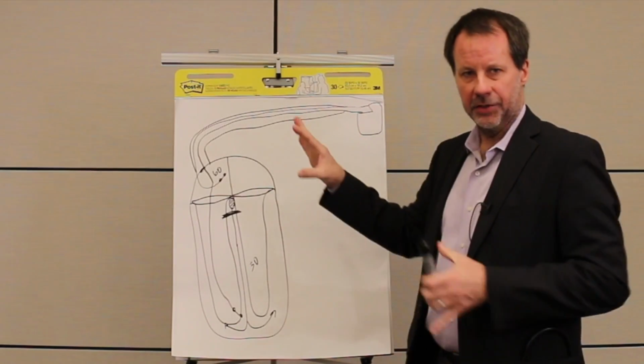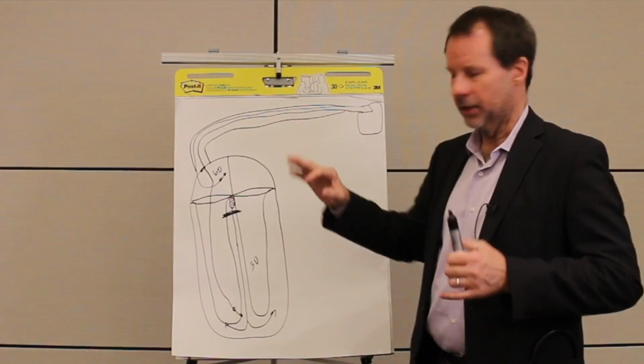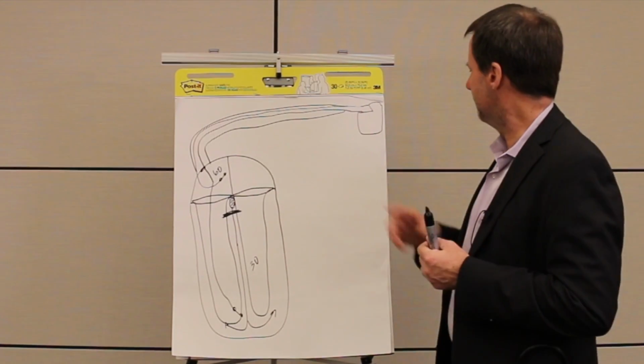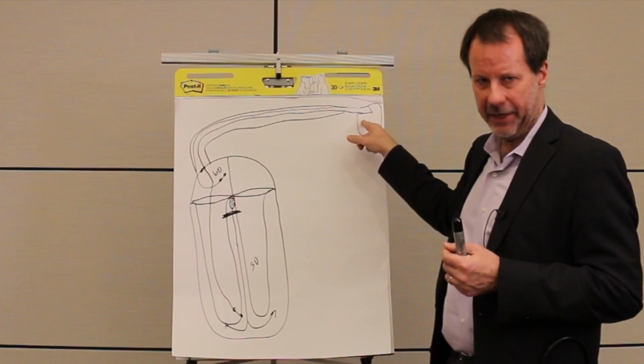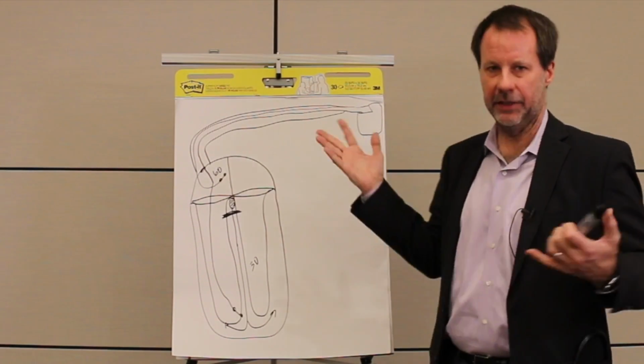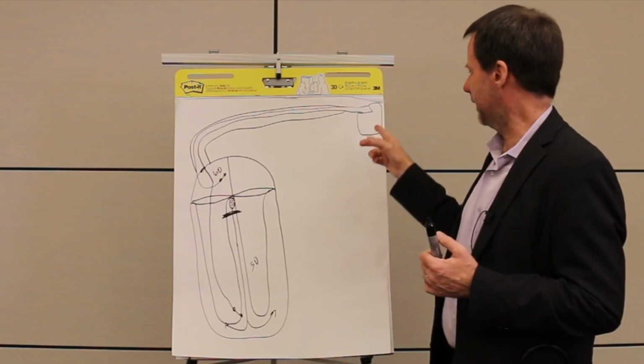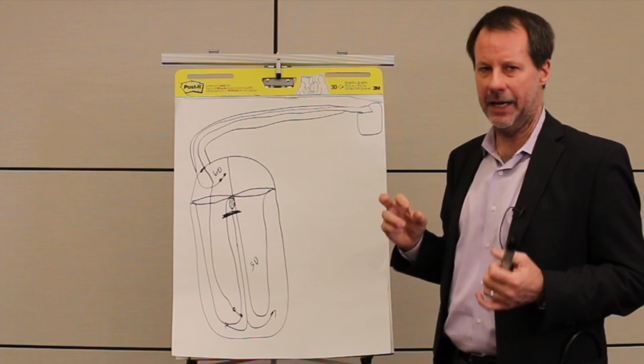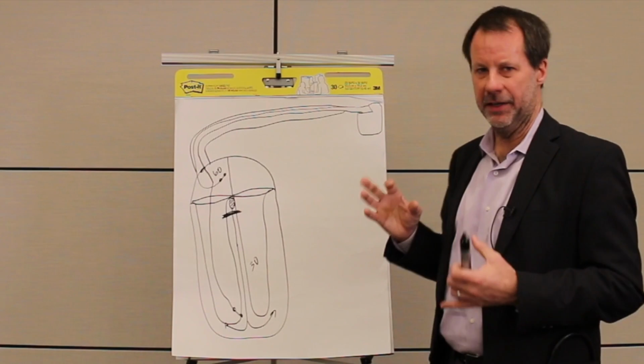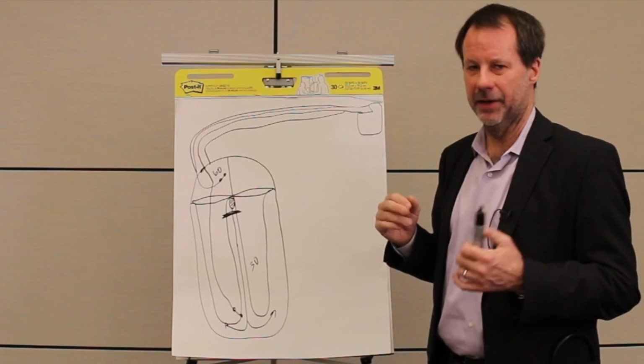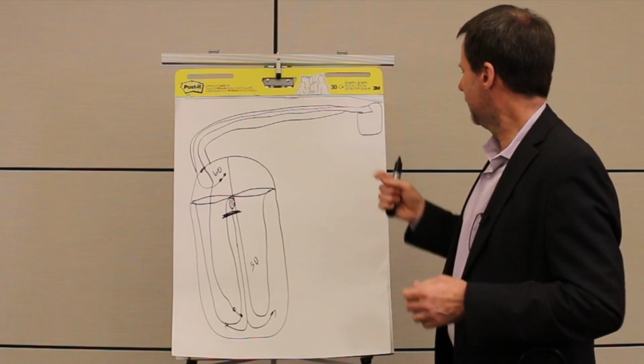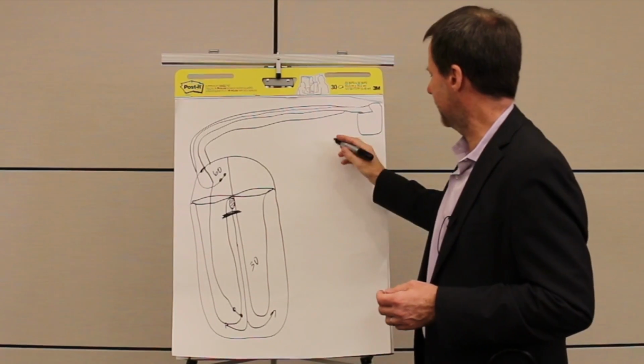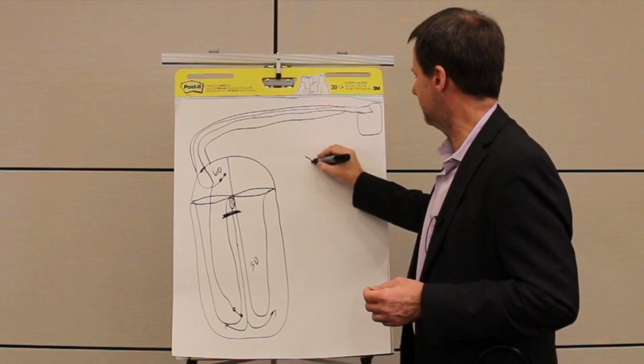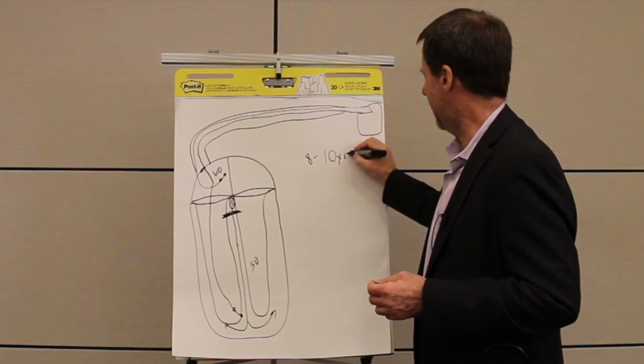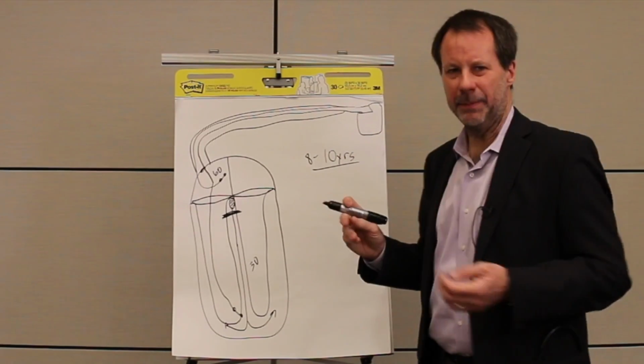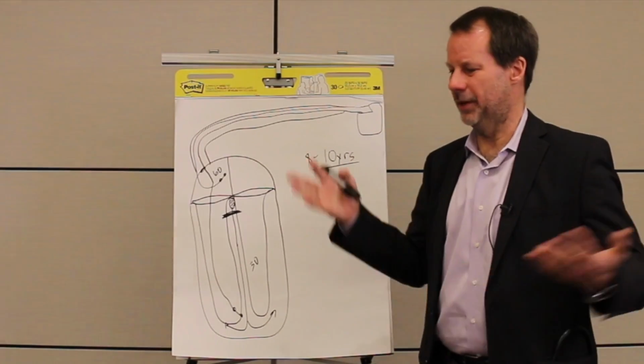So let's say we've got a patient who's got a pacemaker in and everything looks good. How do we maintain that? Well, the pacemaker units run on a battery, and anything with a battery is eventually going to wear out. These devices are very efficient—they don't draw a lot of power, and the batteries are modern and well designed. Most pacemakers will probably get us in the vicinity of 8 to 10 years of battery life.